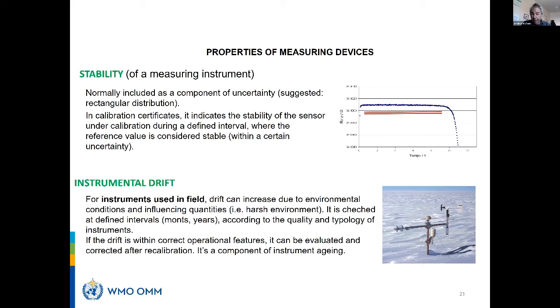You can correct the drift with a new calibration, and you can correct the stability as well. For correcting the drift, you don't have to change anything in your measuring system. But to correct for stability, you may want a better readout system or electronics, or to check your grounding and the overall electromagnetic noise in your lab. That's another way to help reduce the problem.